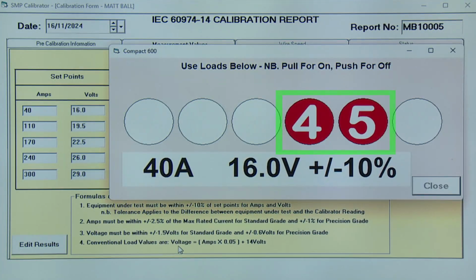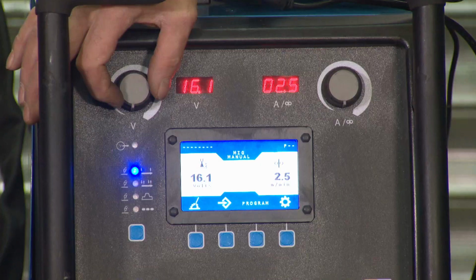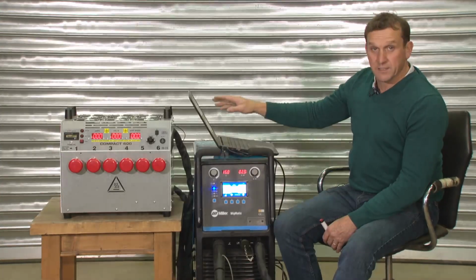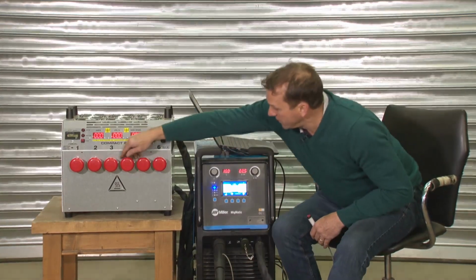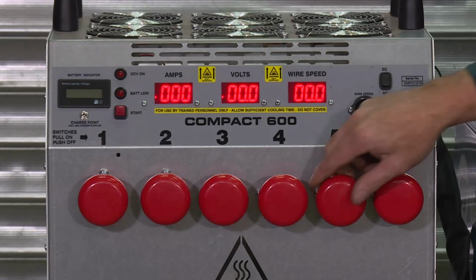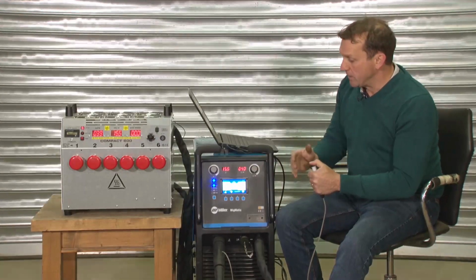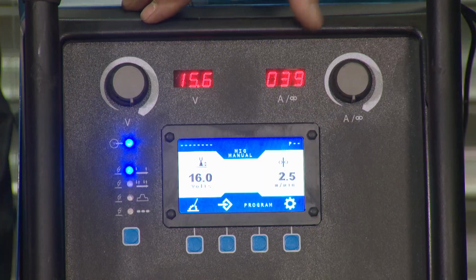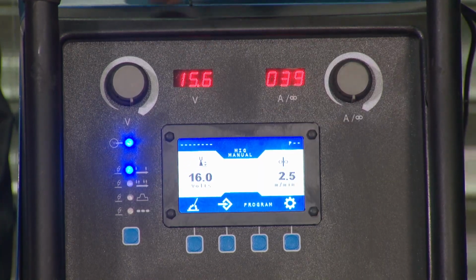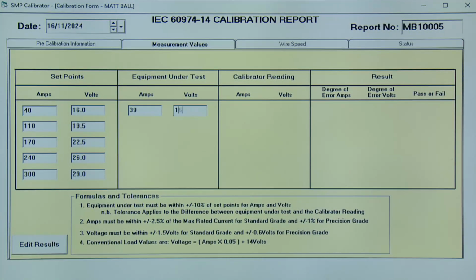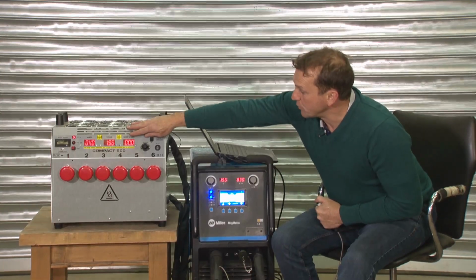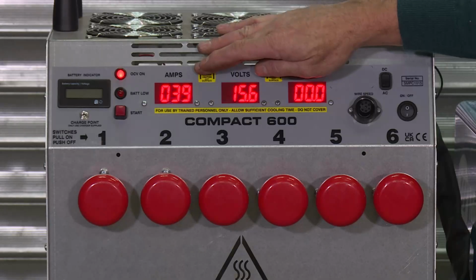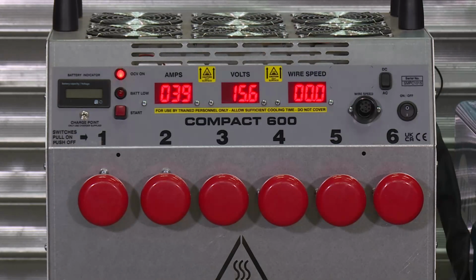At this point the program will actually point out which loads we need for the correct voltage. So we're looking for 40 amps at 16 volts. So we set the welder to 16 volts and select loads 4 and 5 and energize. We have 39 amps and 15.6 volts. And then we record the calibrator reading, 39 amps and 15.6 volts.